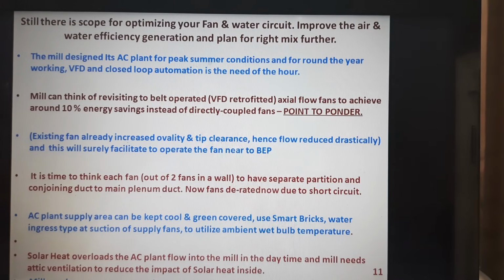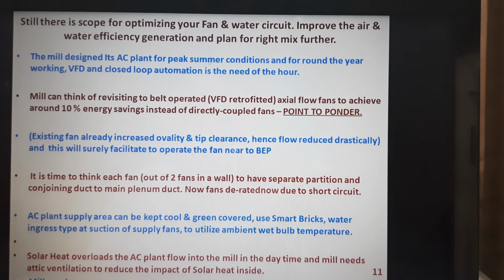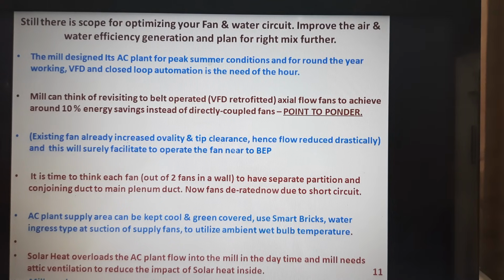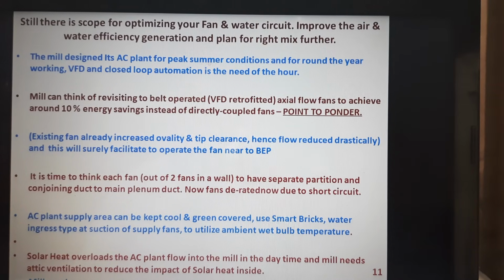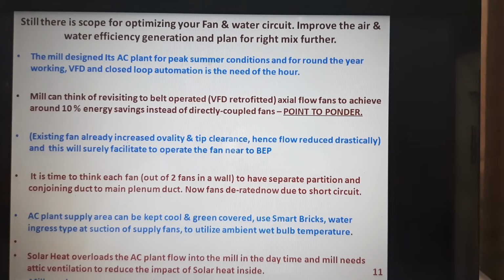Coming to the two fans fixed in each AC plant department, let us try to have a partition and let it have a conjoining duct to the main plenum duct. If two fans are kept in the same space, they are short circuiting, and definitely the fans get derated also due to short circuit. The AC plant supply also needs to be cool and green covered with smart bricks. Water ingress to be there at the suction of the supply fans. It is monitored and controlled, and definitely controlled to utilize the ambient wet bulb temperature.